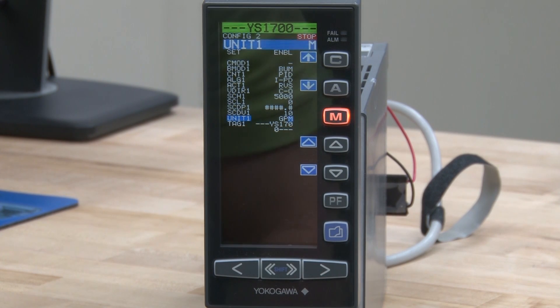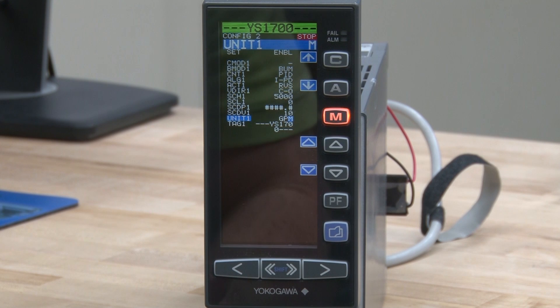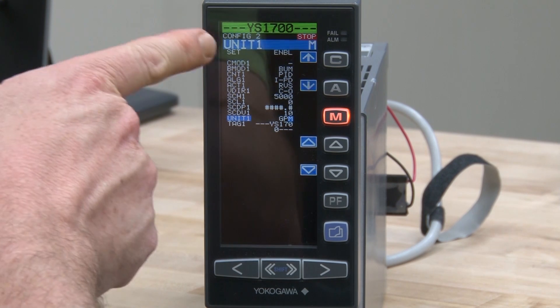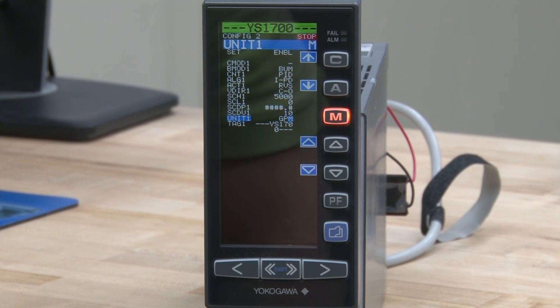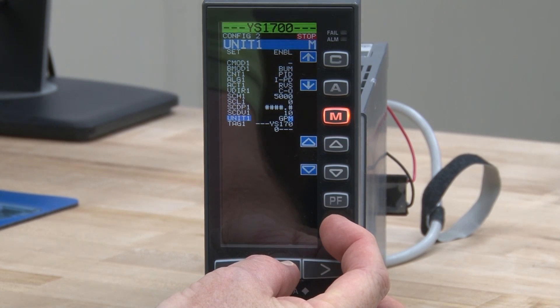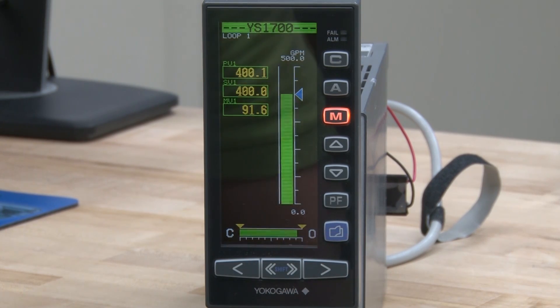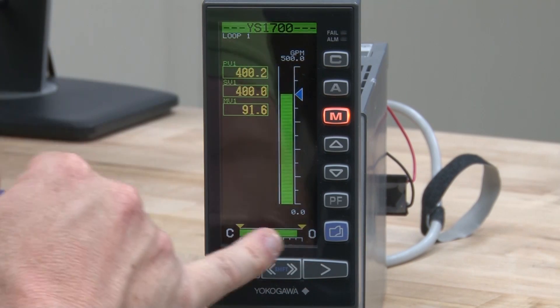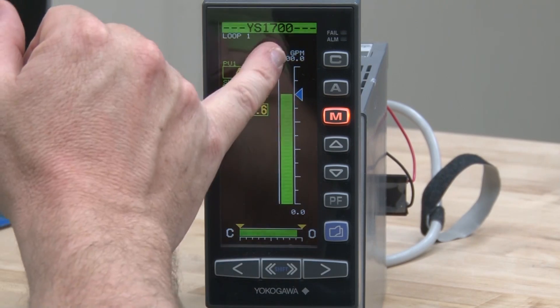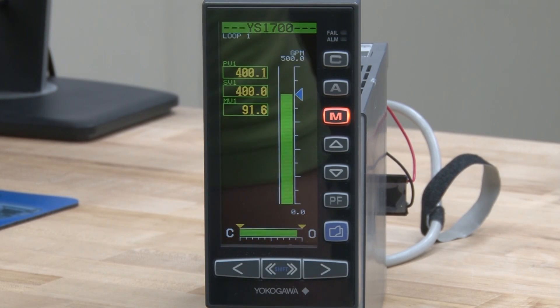Now that's set — we've got the range set up to 0 to 500 GPM. We don't need to push any special buttons to save those values; they are automatically saved on the controller. The SET parameter at the top gets set back to inhibit once we leave the screen. To get out, just hold the shift button and push the page key once. Now we see that our scaling has changed from 0 to 100% to 0 to 500 GPM. That simple.